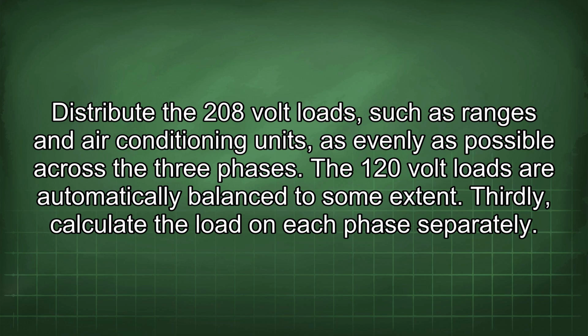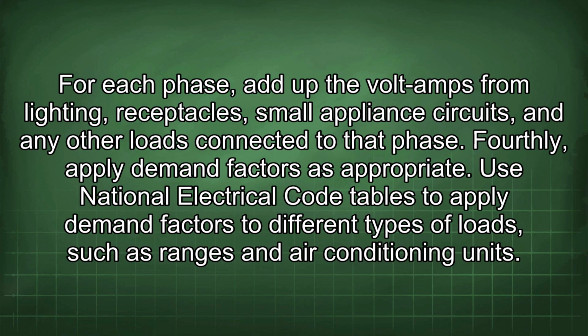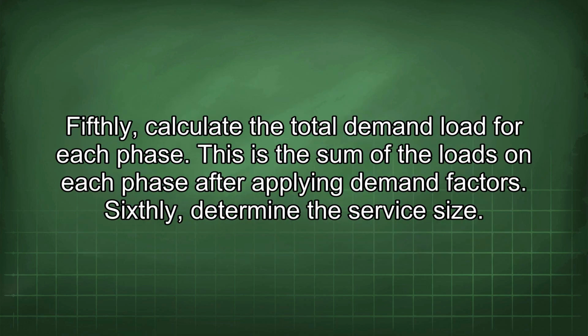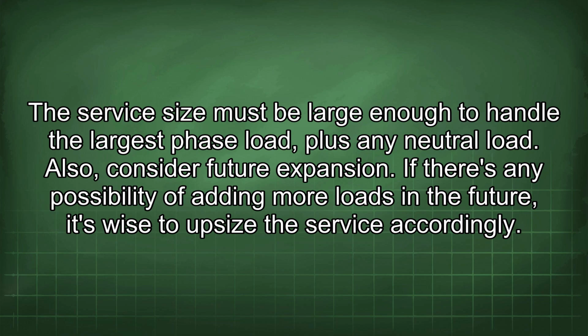Thirdly, calculate the load on each phase separately. For each phase, add up the volt amps from lighting, receptacles, small appliance circuits, and any other loads connected to that phase. Fourthly, apply demand factors as appropriate. Use National Electrical Code tables to apply demand factors to different types of loads, such as ranges and air conditioning units. Fifthly, calculate the total demand load for each phase. This is the sum of the loads on each phase after applying demand factors. Sixthly, determine the service size. The service size must be large enough to handle the largest phase load, plus any neutral load.